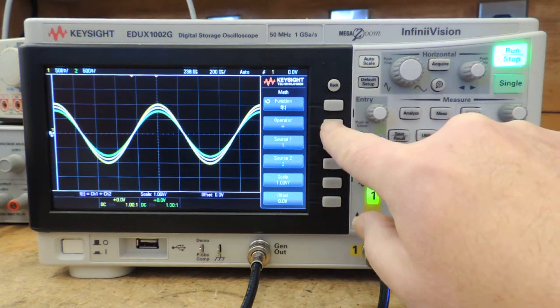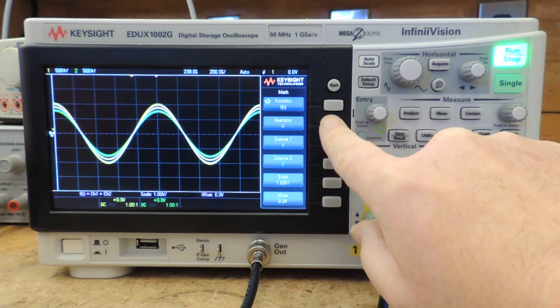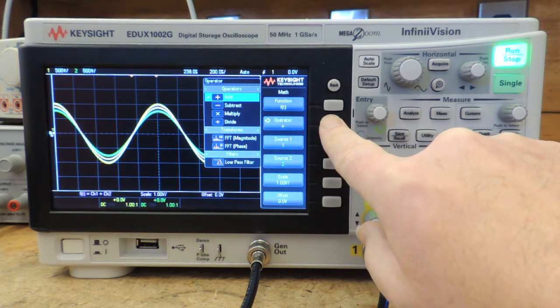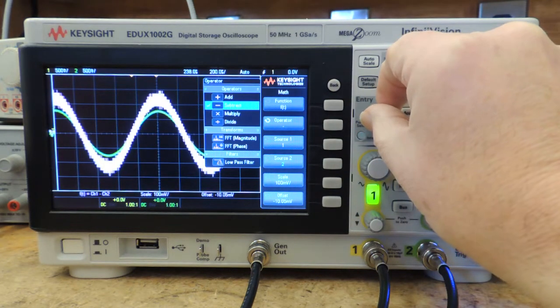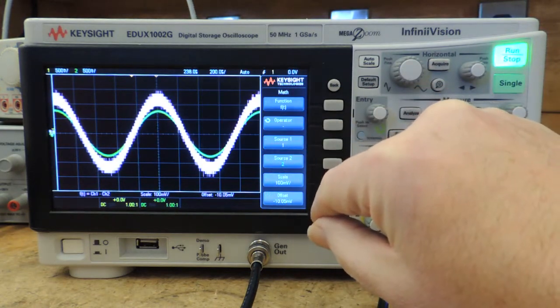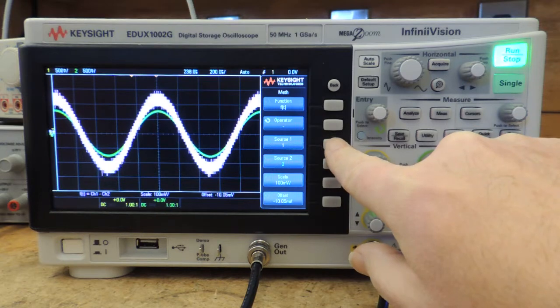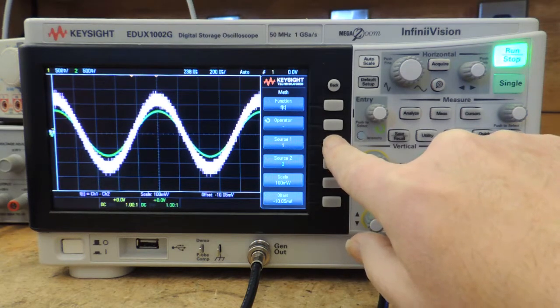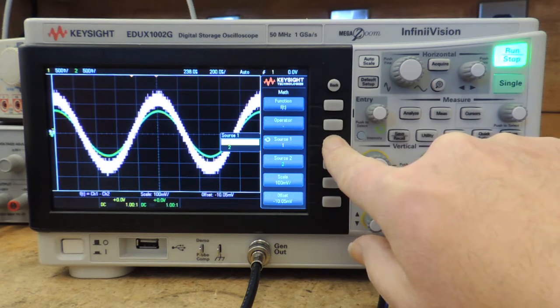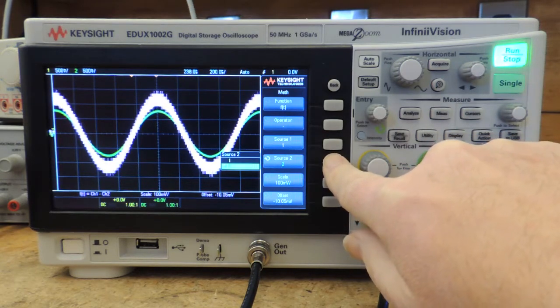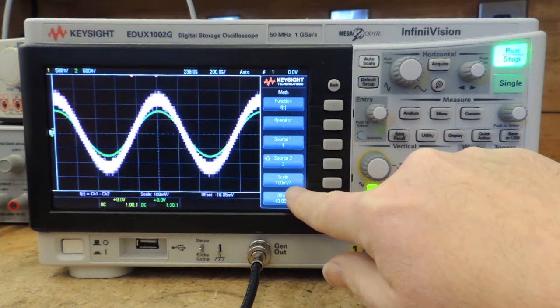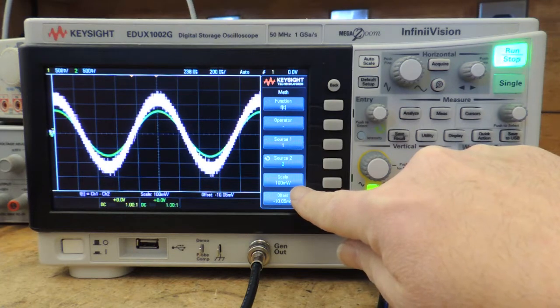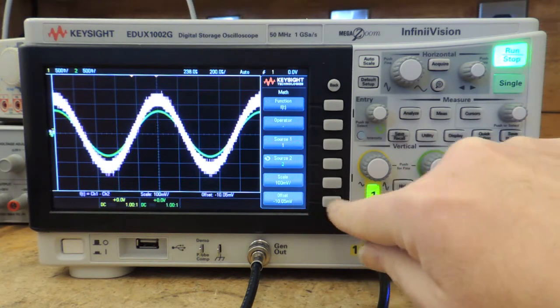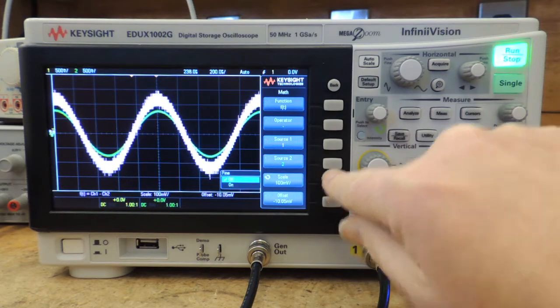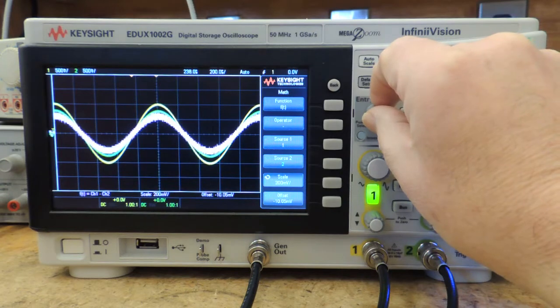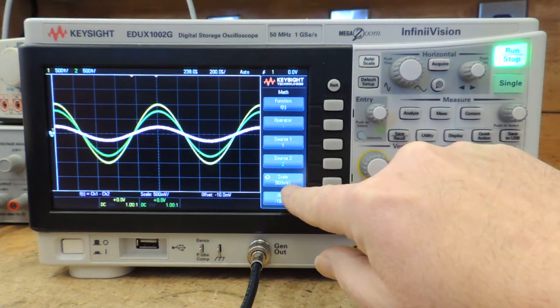So, function is okay, but the operator is plus. We want the operator to be minus. So, select operator, and then we can use the entry knob to select subtract. What are we going to subtract? We have source 1 is channel 1, and source 2 is channel 2. Now the scale is 100 millivolts, so we want it to be on the same scale as channel 1 and channel 2. So I'm going to press my scale button and rotate my entry knob until it is at 500 millivolts.